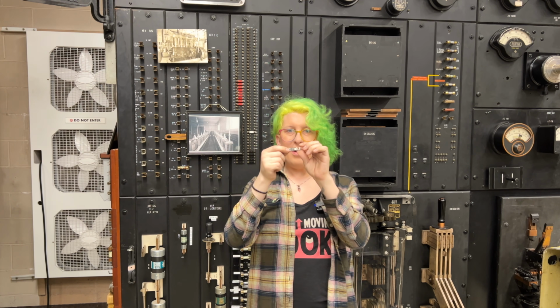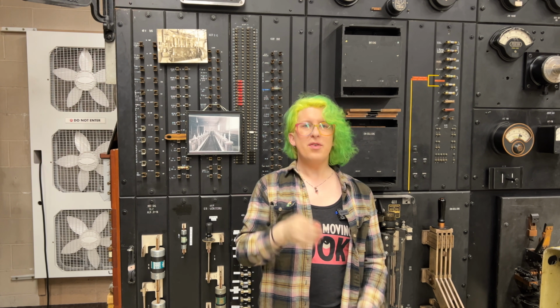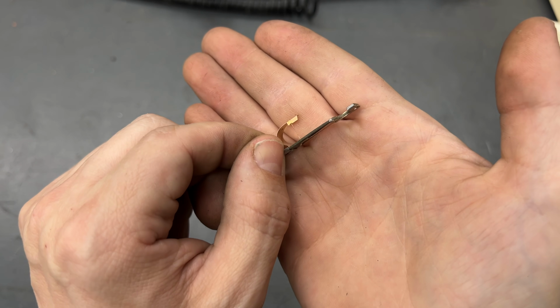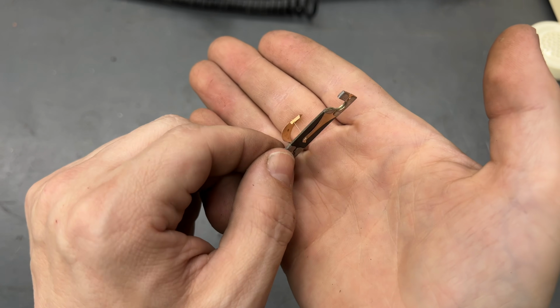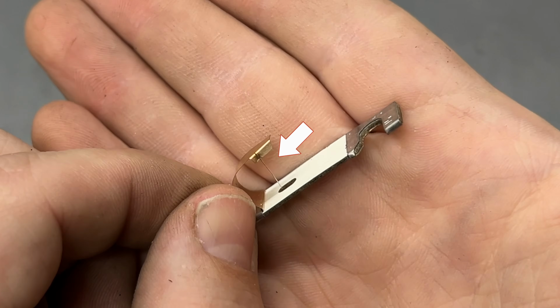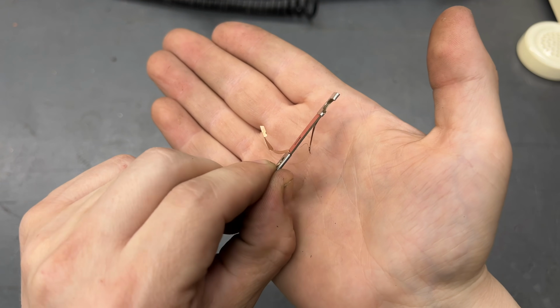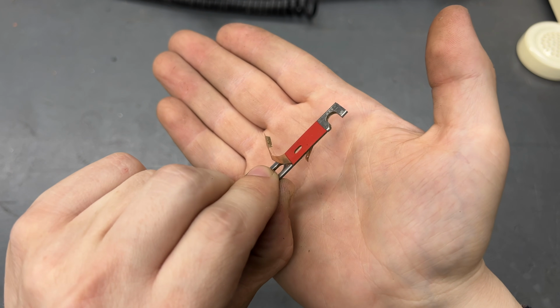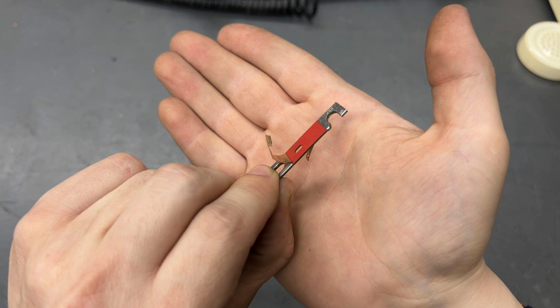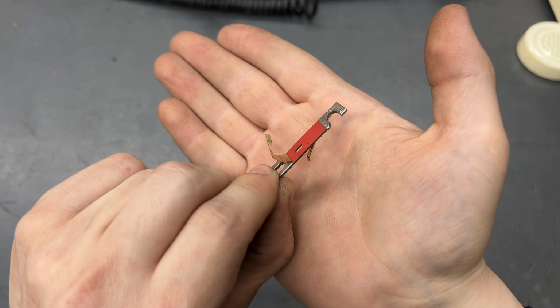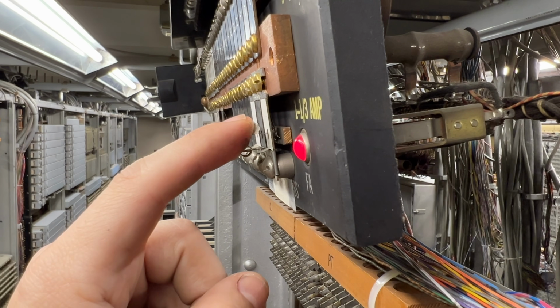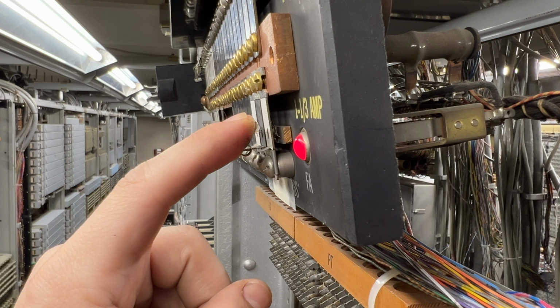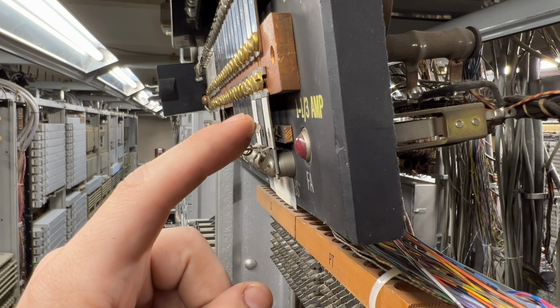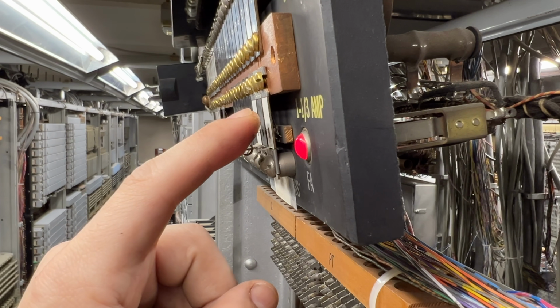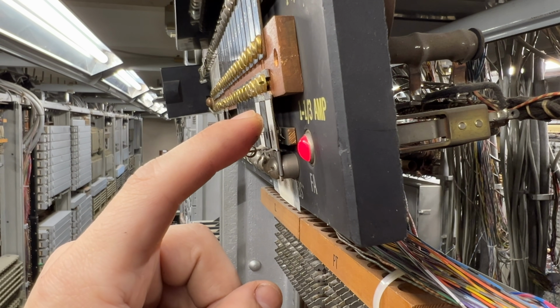These fuses are quite clever, and they have a bit of a story behind them. The reason we call them grasshopper fuses is because of these little tabs at the front and back of the fuse. When the fuse is in its normal state, the tabs are held in by the fuse wire. When the fuse blows, the fuse wire breaks and releases the tension holding the tabs in. The front tab pops out towards the user and serves as a visual indication that the fuse is blown. The rear tab contacts an alarm bar on the fuse panel, which diverts the 48 volt power to the office alarm circuit and rings the major alarm gong. Lamps throughout the exchange guide craftspeople to the source of the blown fuse so it can be quickly replaced and the equipment put back into service.